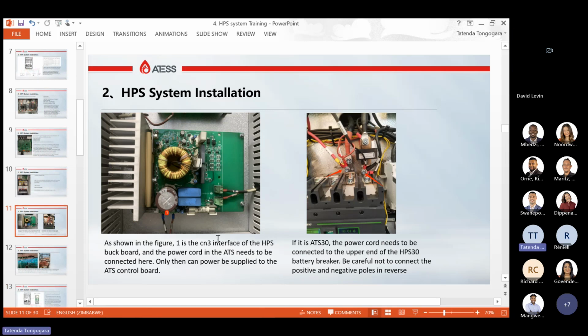And then inside the HPS, we have our buck board. This one is the one that powers the ATS. Inside the ATS, there is no power supply, so you have to power the ATS through the buck board. Your ATS power should come from this, because if you connect it on your AC input, the moment you lose your AC input, your ATS will go off. So it's best you power it from the battery.